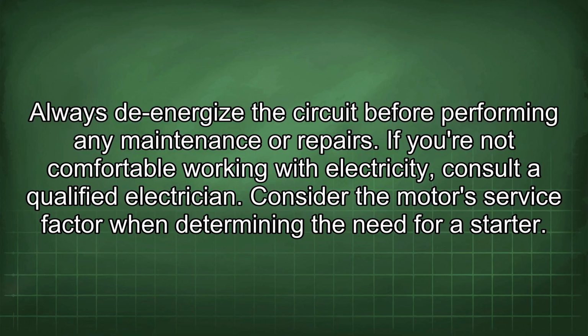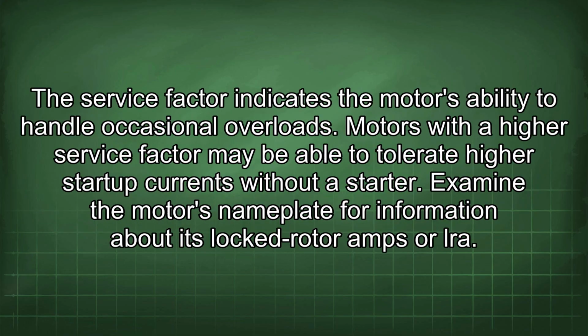Consider the motor's service factor when determining the need for a starter. The service factor indicates the motor's ability to handle occasional overloads. Motors with a higher service factor may be able to tolerate higher startup currents without a starter.